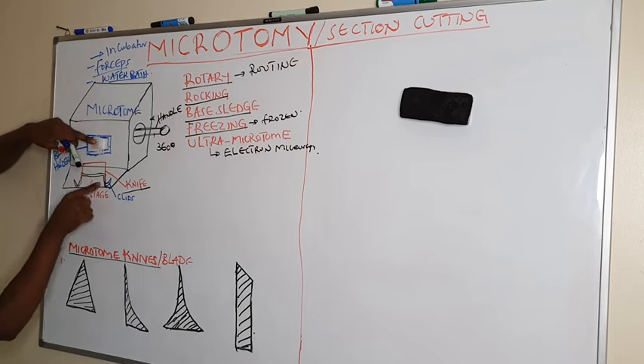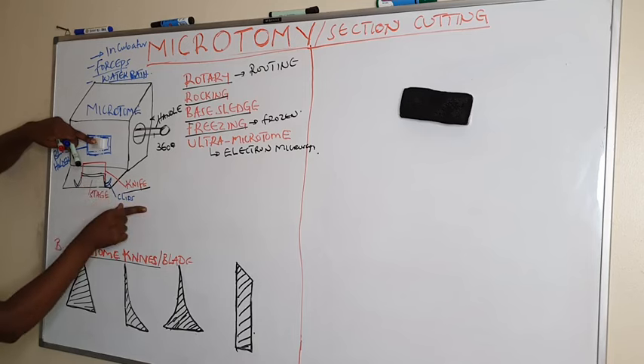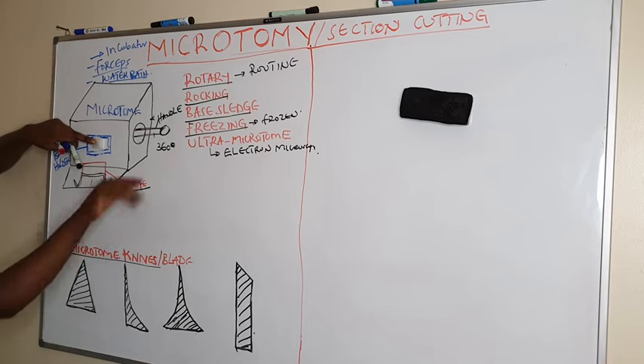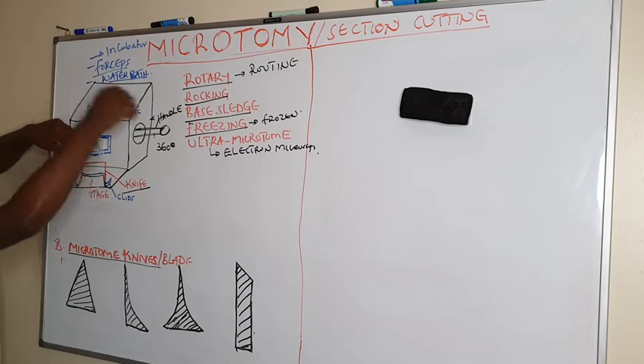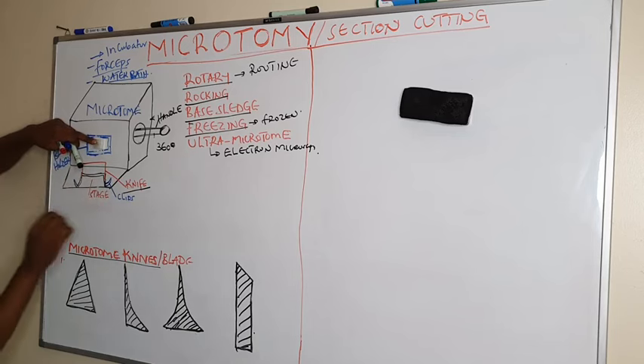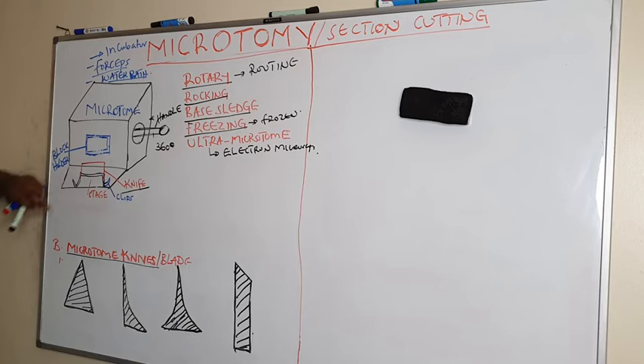The knife is always clipped on the stage — this is the stage of the microtome, and the knife is fixed by the clips tightly. So when we move the handle, the block on the block holder moves past the stationary knife. This is the rough structure of the rotary microtome.